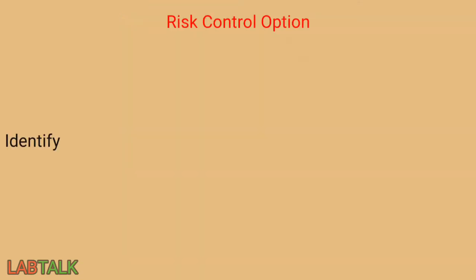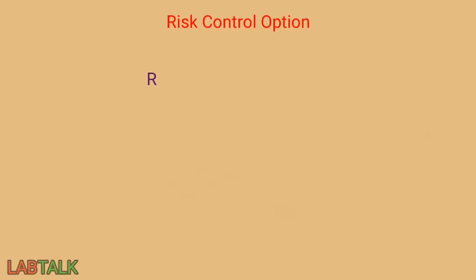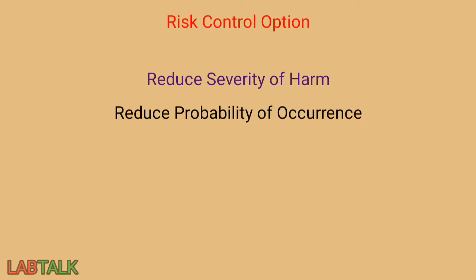The laboratory shall identify and implement verified risk control measures that reduce the risk to an acceptable level or can completely eliminate the risk. The risk control measures can reduce the severity of the harm and reduce the probability of occurrence, or can be useful in both. While selecting risk control measures, we have to prioritize some of the measures.